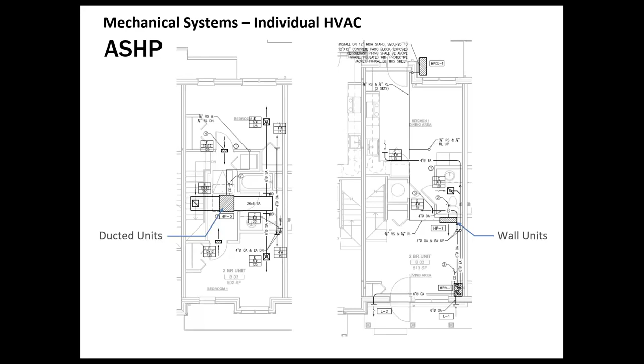And then similar to the air source heat pump, there is the VRF, or the variable refrigerant flow type systems, which use the same wall units and ducted heat pump indoor units, but use a single centralized outdoor condensing unit in order to control all of the interior units at once. Then there is, of course, a complicated switching and management system to be able to send refrigerant to where it is needed at the temperature that it is needed. So one side of a building can be getting cooling while another side could be getting heating, or one unit could be heating while another unit is cooling.